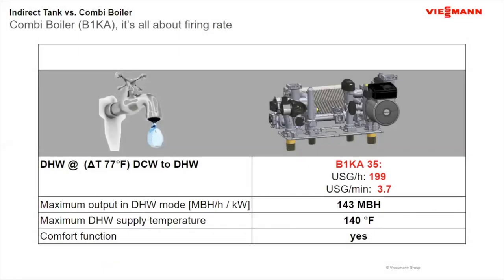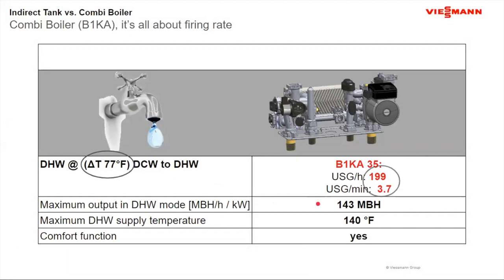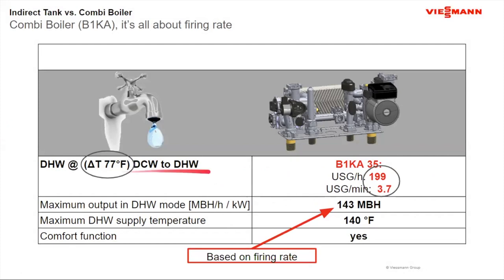Now, with a combi boiler, as we said earlier, it is all about performance. It's all about input. So when I look at a combi boiler, I'm always going to deal with the output of the boiler. And this is kind of where my 150,000 number came from. I have a 150,000 BTU boiler. The boiler's output's probably going to be about 143,000. And at a 77 degree temperature rise, I can get about 3.7 gallons of hot water. Okay. And this is also a priority mode.